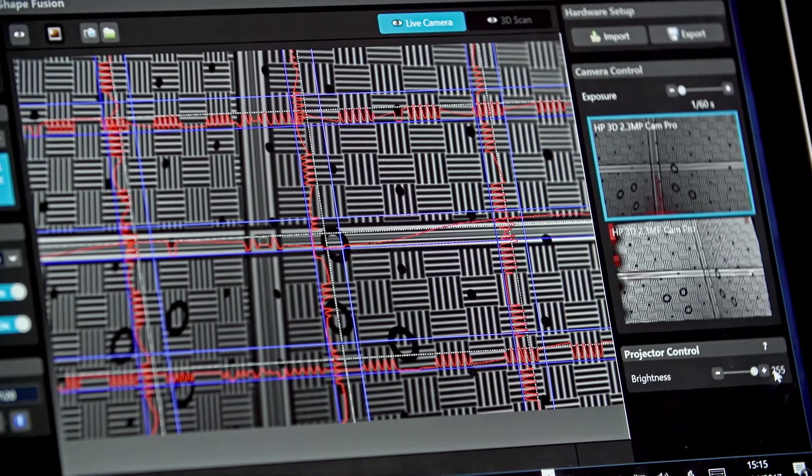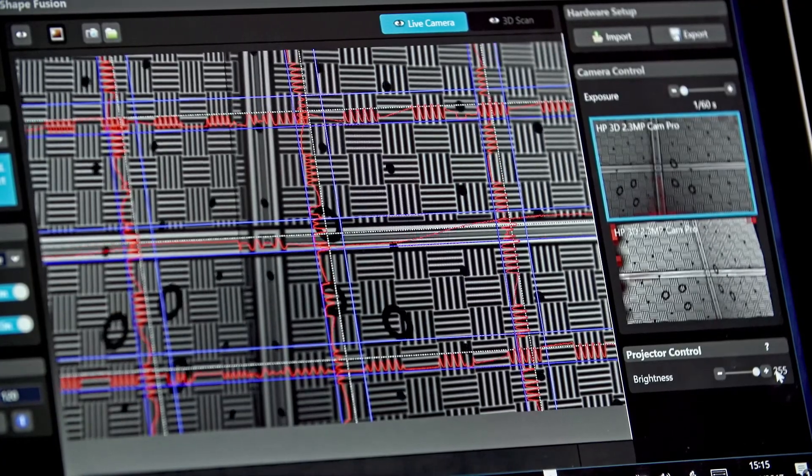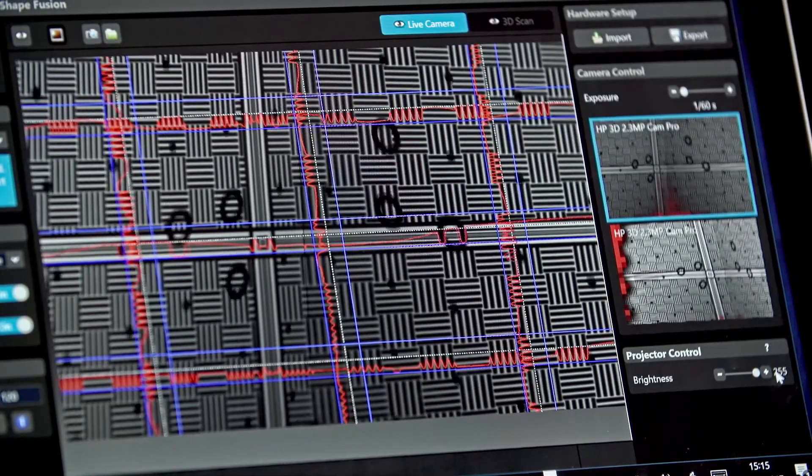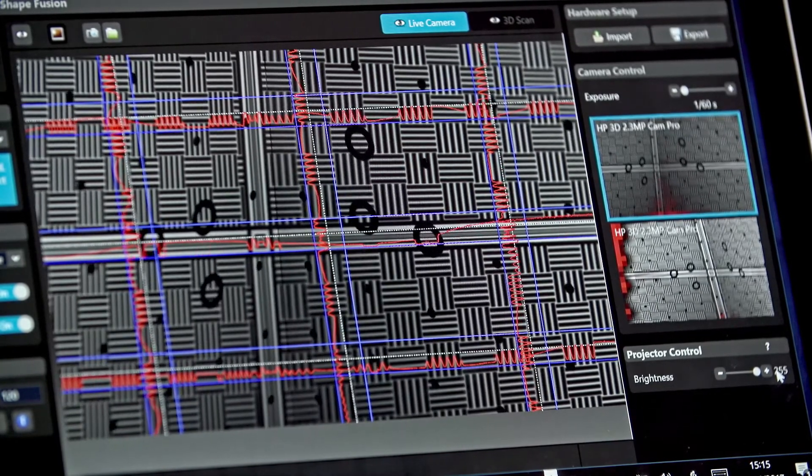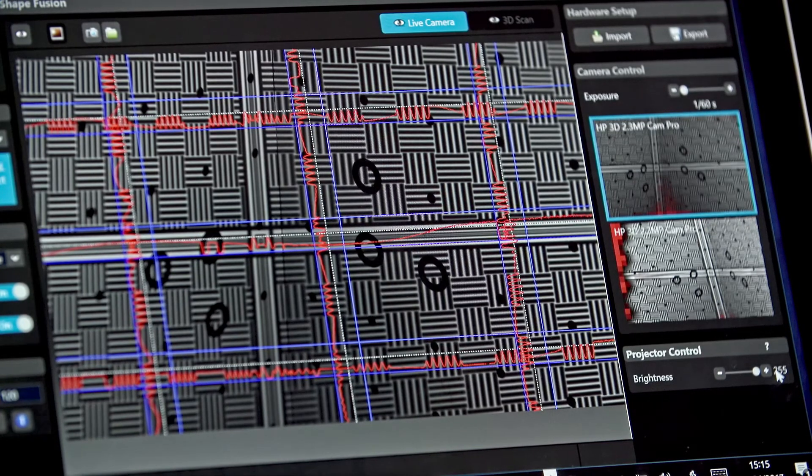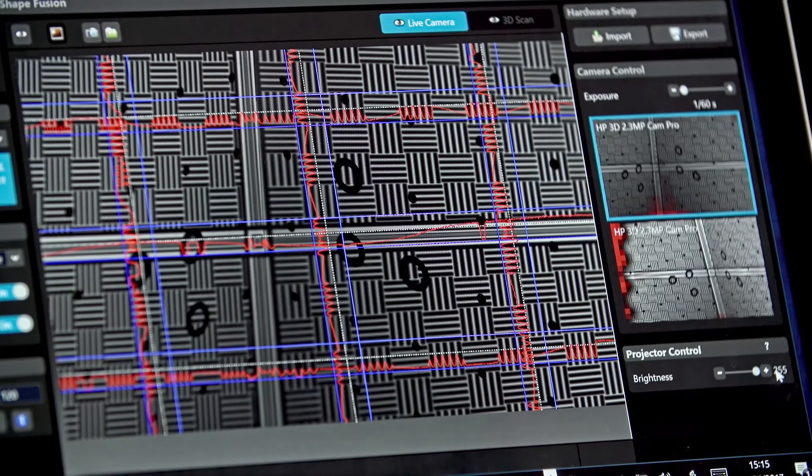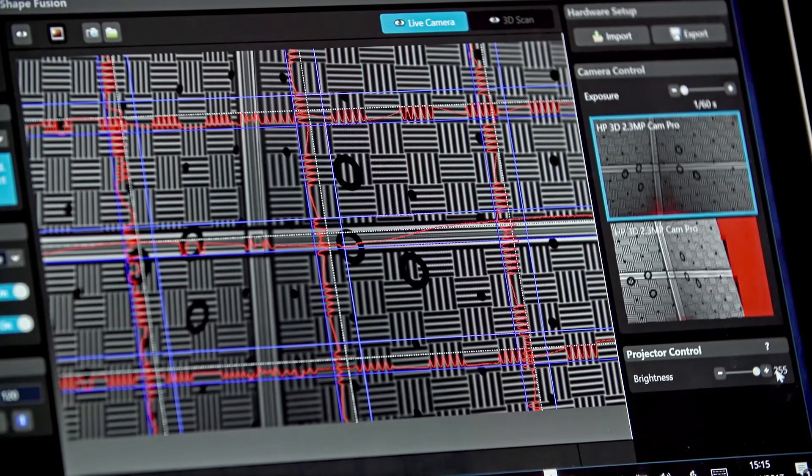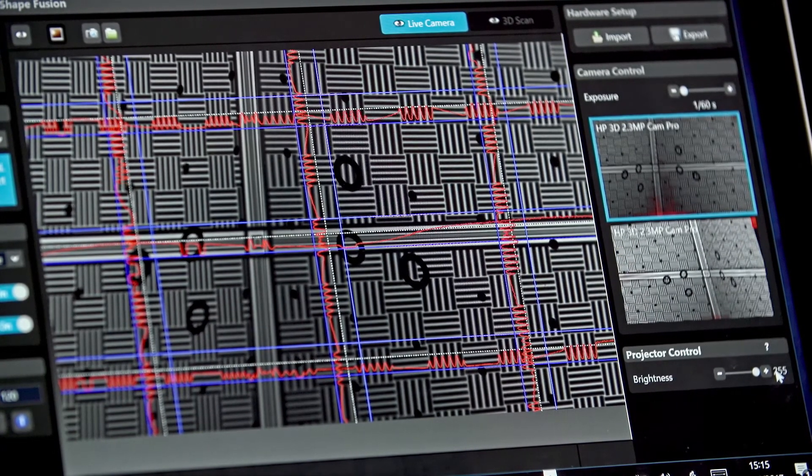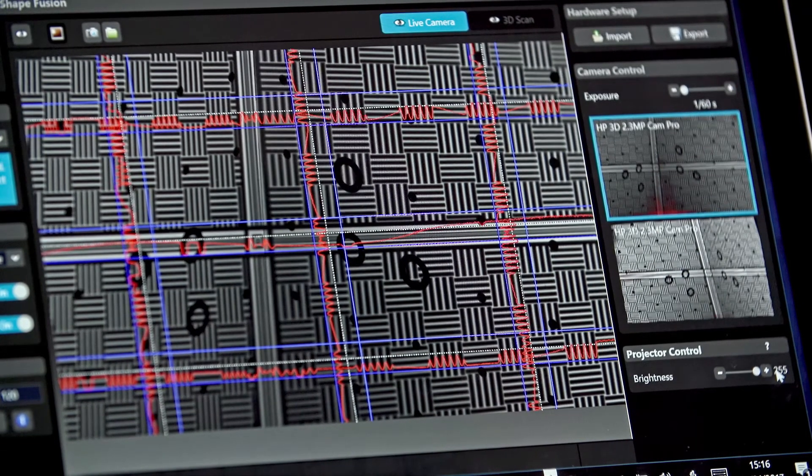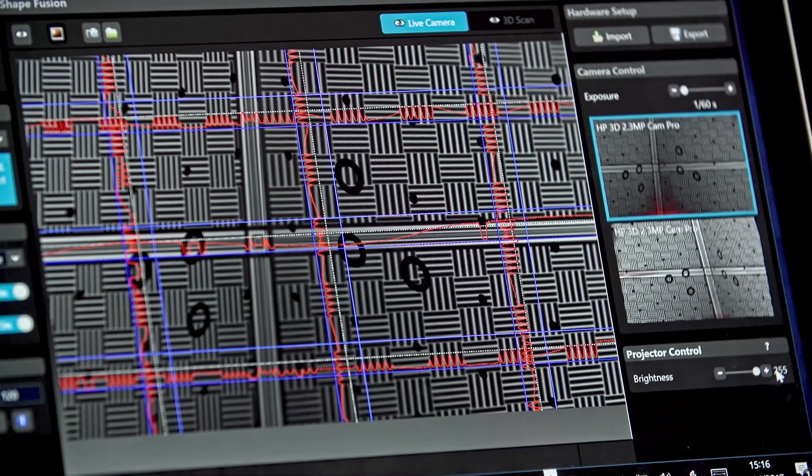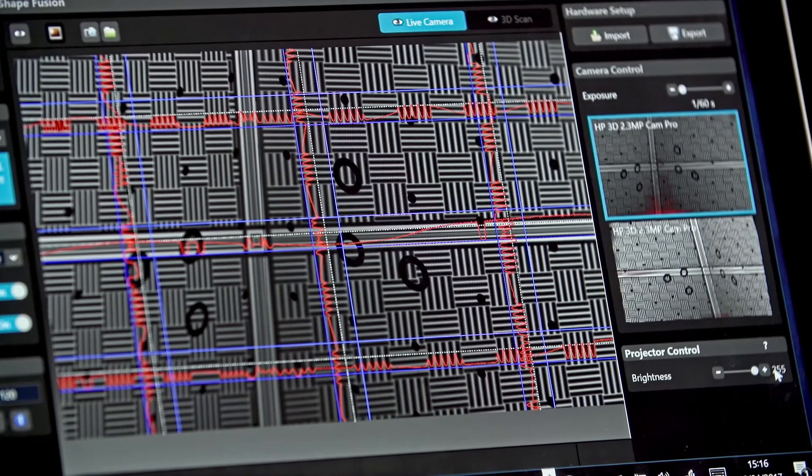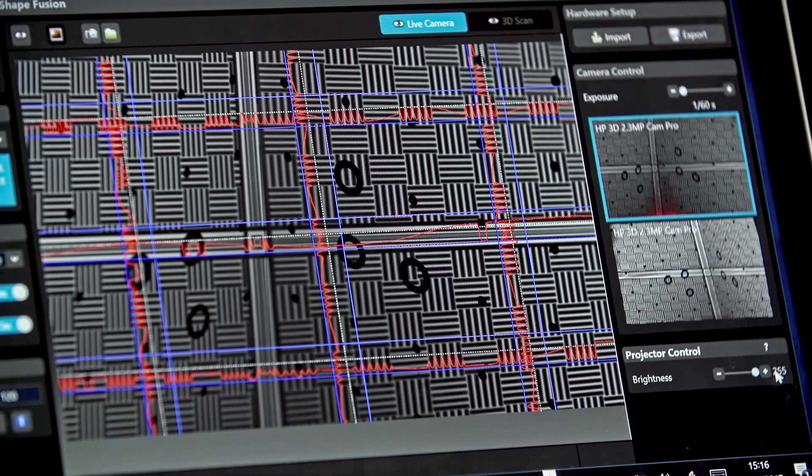You must be able to see all six rings and 15 to 70 calibration markers in both camera view windows. The cameras and projector should not look at too flat an angle and the camera views should not extend aside the panel. When using dual camera setups, the rings and other points must be visible to both cameras at the same time. Move and twist the panel to ensure rings and calibration points are properly oriented. Look at the camera view windows in the software.